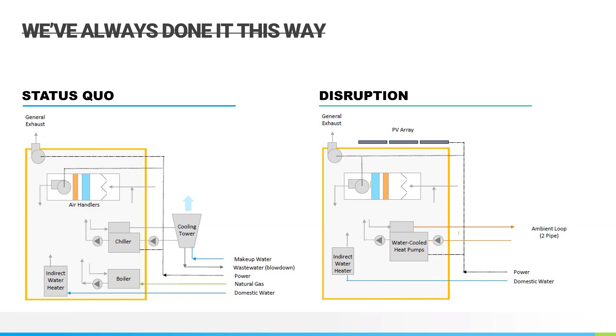So you're no longer even having natural gas to the building. You can see that green line was completely eliminated. And that was one of the big goals of this campus, to dramatically reduce natural gas consumption and actually eliminate the infrastructure where it could be. There were some areas for medical purposes and other things like that where they needed natural gas to exist, but most of the areas, it was definitely not being used for heating or hot water production on the entire campus.